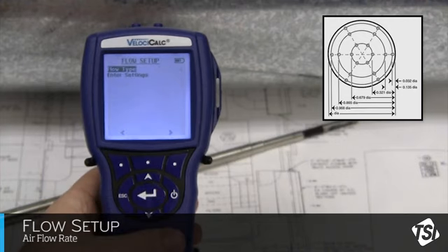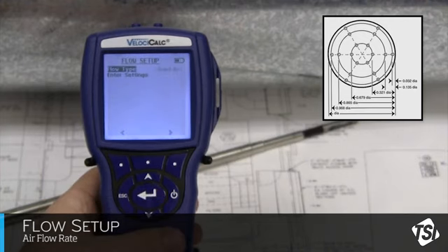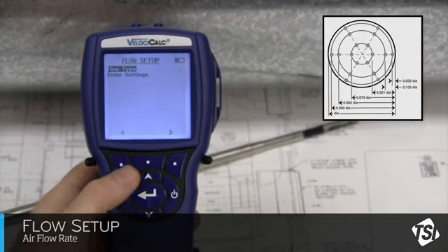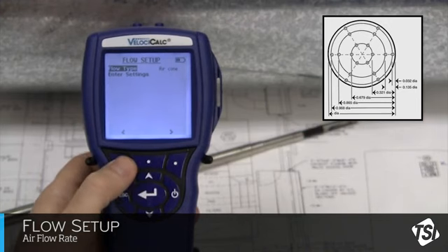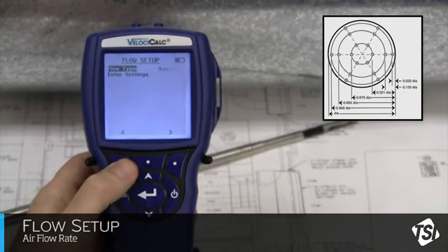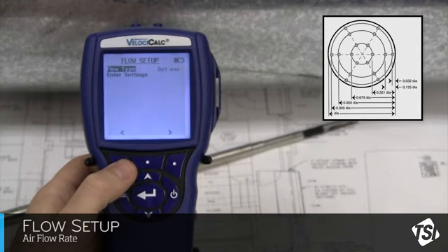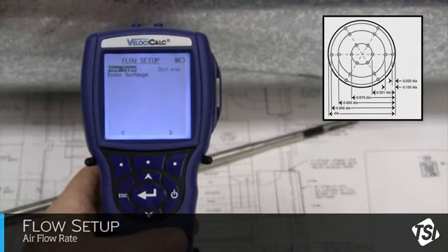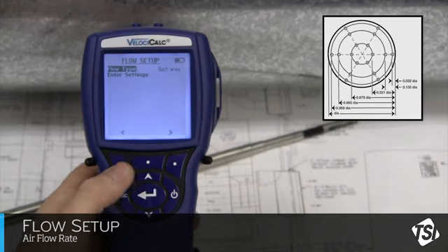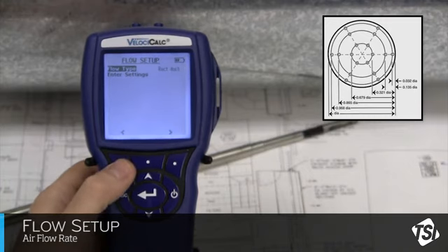Use the right or left soft key to scroll through the duct options. You have the option to select Round Duct, Rectangular Duct, or if you already know the square footage of the duct, you can use Duct Area. There are other options as well. For the purpose of this example, let's assume we are measuring in a round duct.